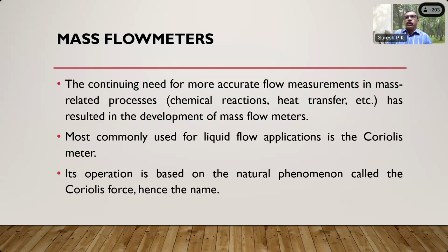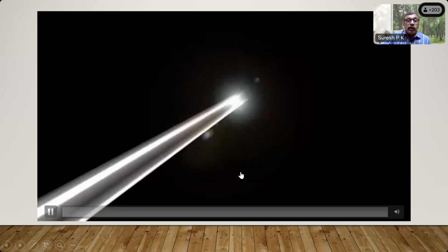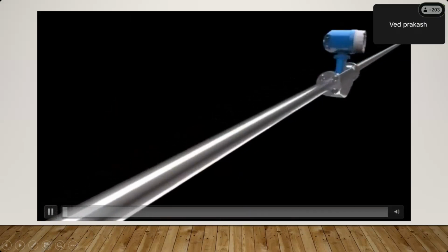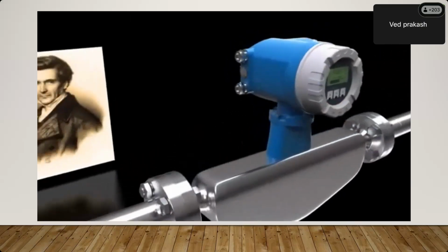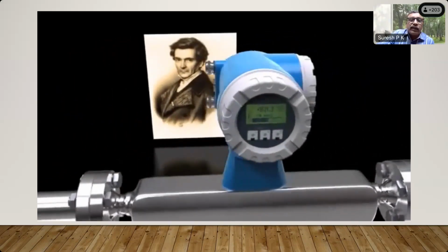Basically, the Coriolis force correction is done even in rockets. The air which is moving from, say, the South Pole to the North Pole is moving across radially, and since the Earth is rotating, it also experiences a Coriolis force which will make a directional change in the air. The same principle is made use of in this flow meter, the Coriolis flow meter. Again, the commentary is not there, so I'll try to explain in the background.